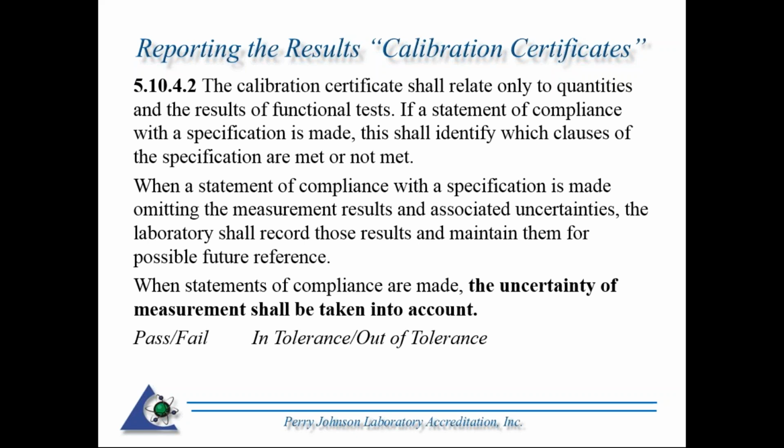So this is saying when you say something passes or fails, in tolerance, out of tolerance on a certificate, that it is clearly within there. You have some instances where you have a gray area. You're saying something passes, however, uncertainty may actually push it over the limit.